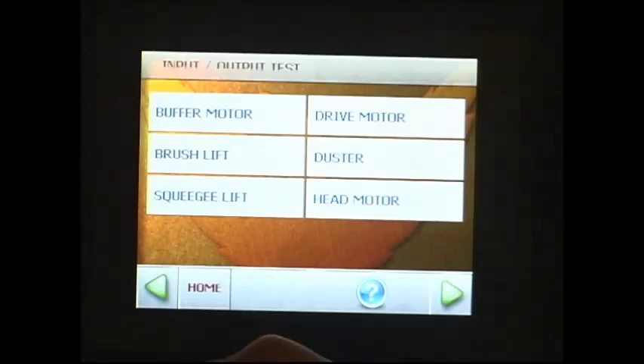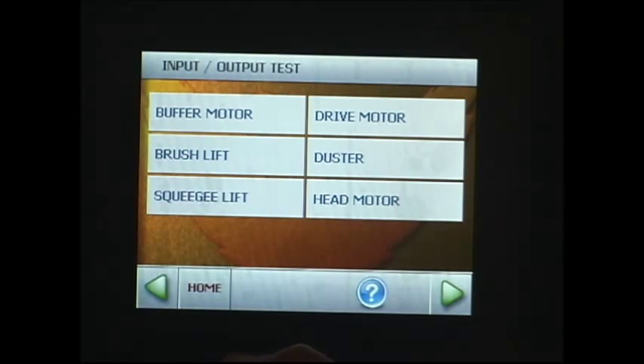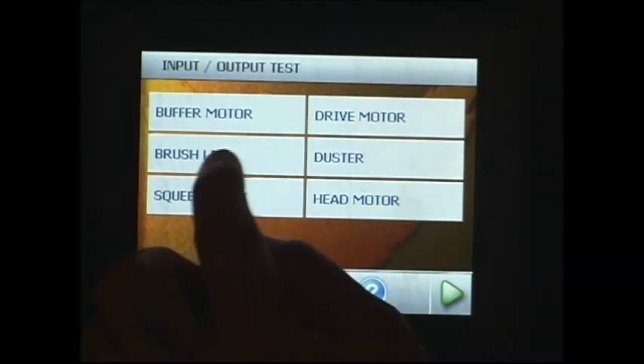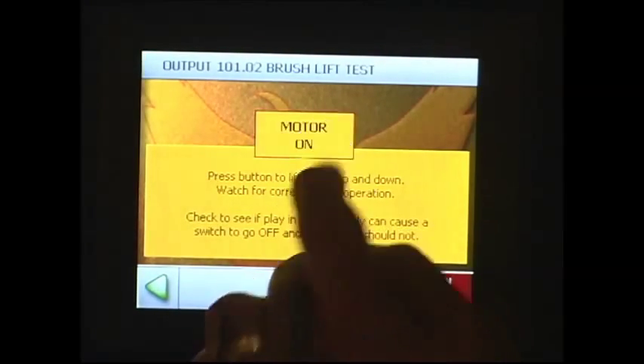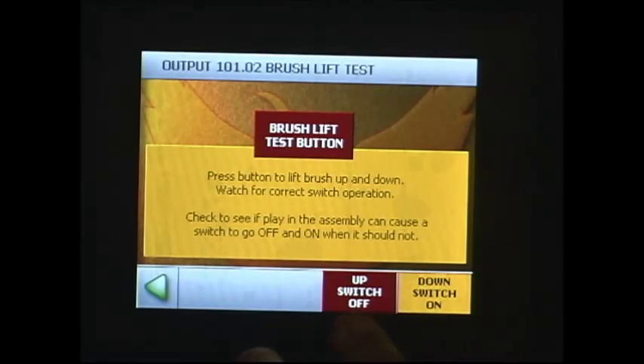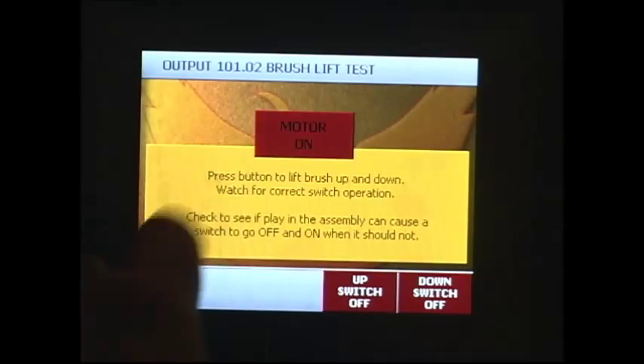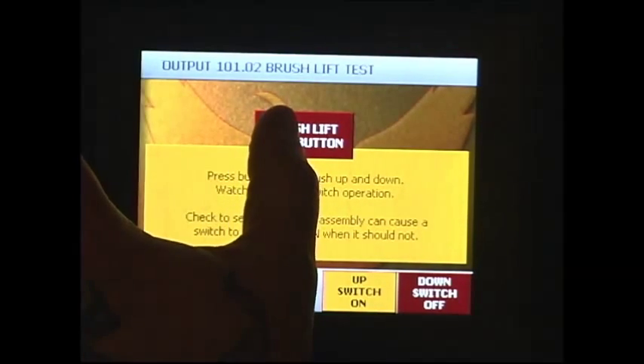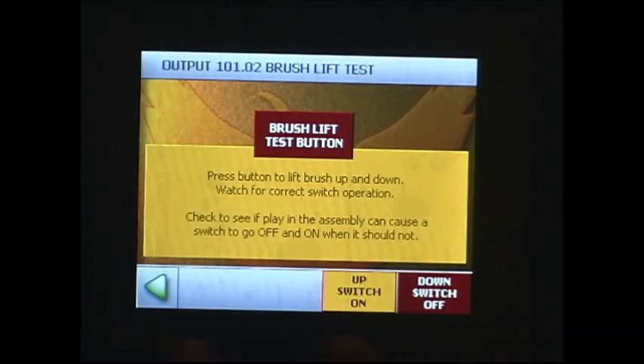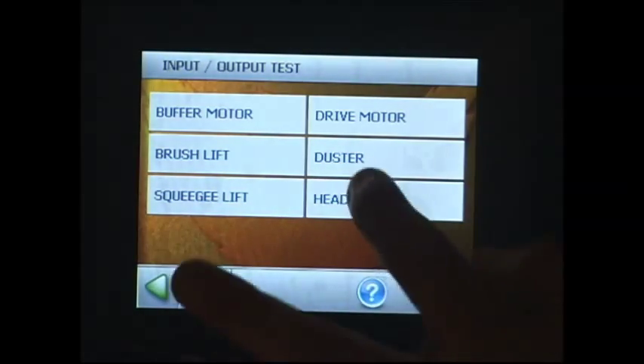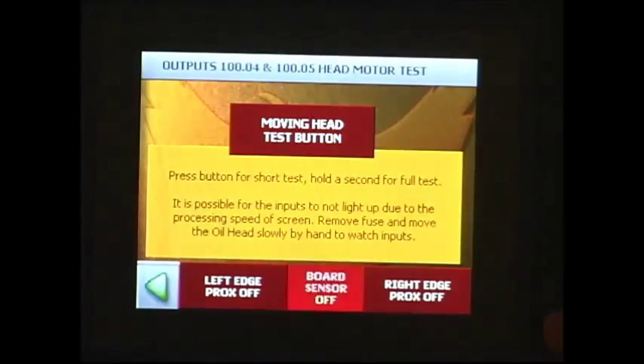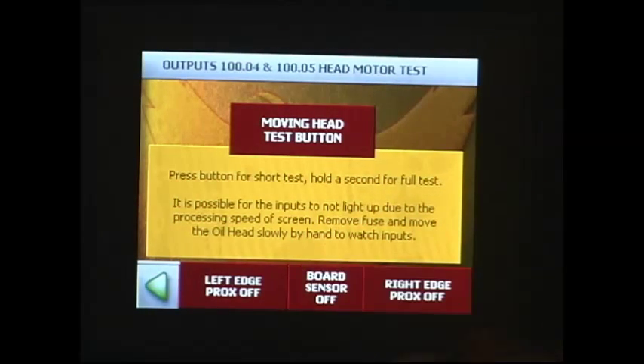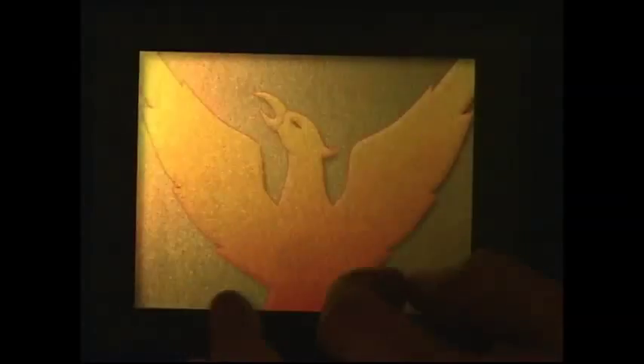Input-output test. This is something that's very important. If you are having trouble with the machine, this is where you want to go to physically test those outputs to make sure that they're working. Just like, for instance, brush lift, you can come in here and turn that particular motor on. And then there at the bottom of the screen, you'll see the input switches making contact. If there is a problem with one of the input switches, you can locate it right here. Head motor, make the head move. Duster, you can unwind the cloth, wind it up.